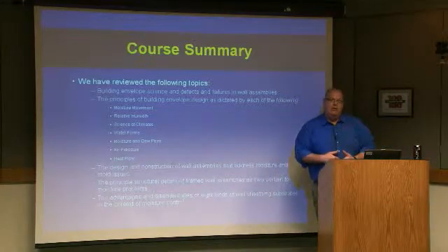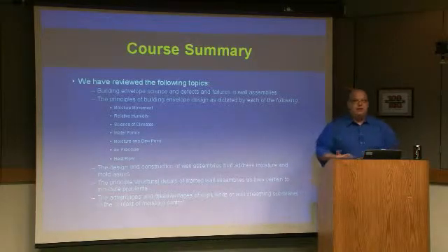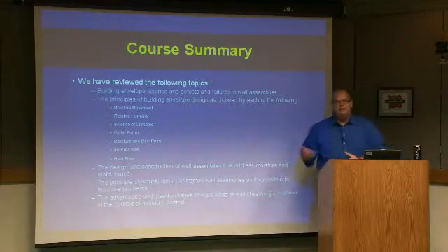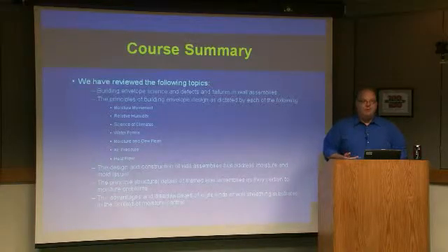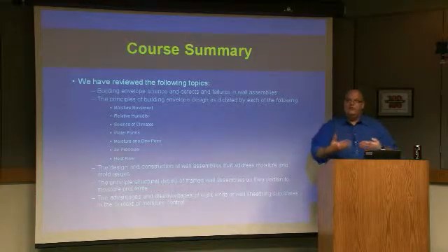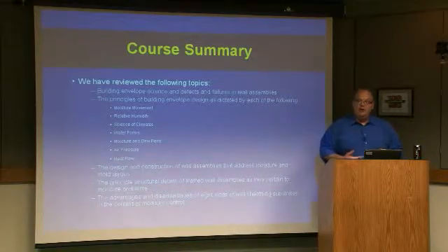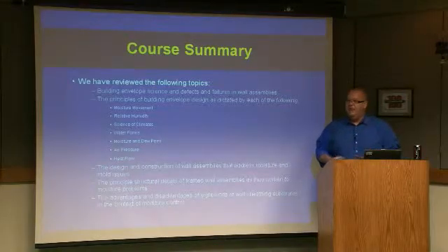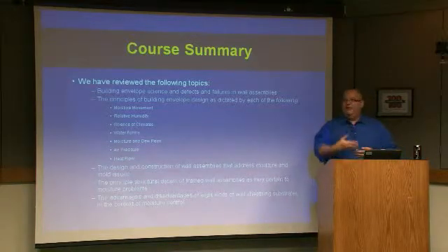If you go too low, you don't breathe enough. You go too high, you breathe too much. That becomes really important when you look at the big market leader out there, say Tyvek. Tyvek is anywhere from 36 to 50 U.S. perms. That is very, very breathable. That becomes very important when you have a wall that has a moisture storage cladding. If the exterior surface of the wall can store moisture, every time it rains, it's going to do that. Every time the sun comes out, the sun's going to heat up that wall and evaporate that moisture, creating a very high humidity and temperature, and at that point a very high vapor pressure, which is then going to try to drive straight through the wall. How quickly it goes through depends upon the resistance of the layers in between.